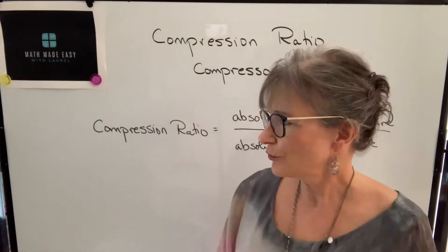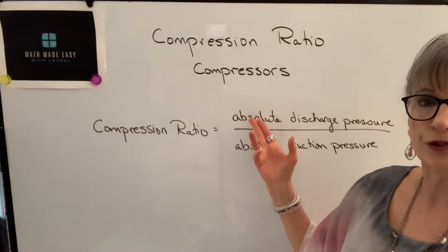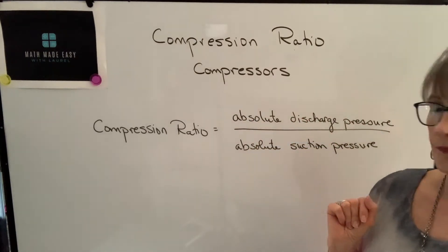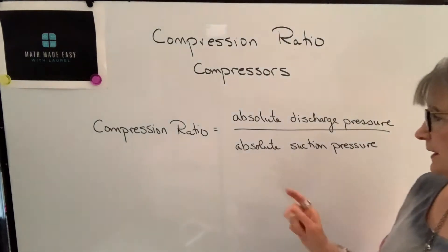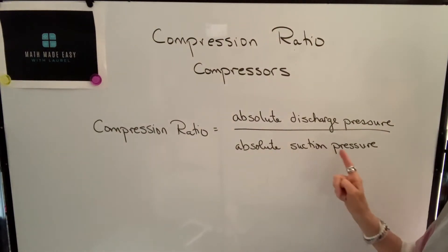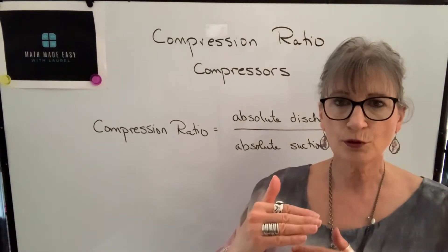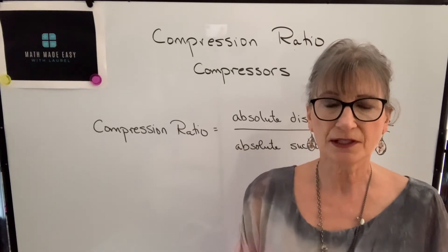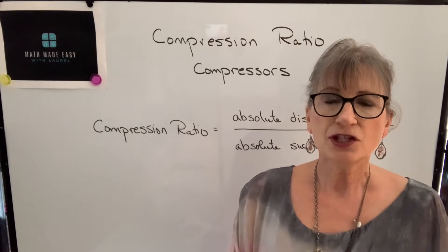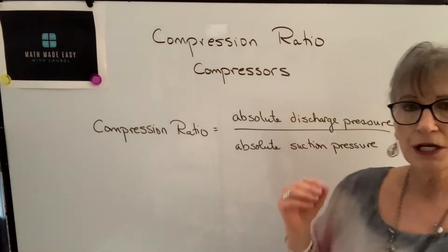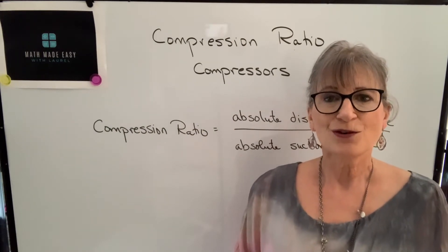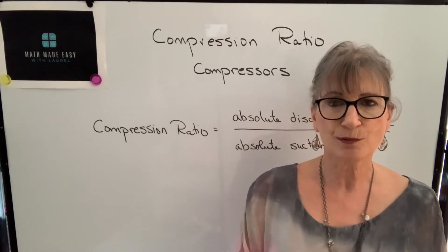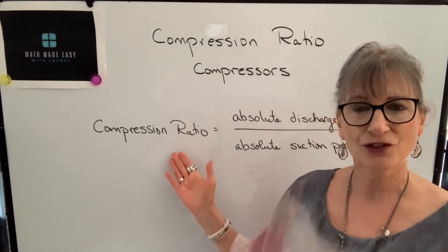The definition of a compression ratio is a ratio between two pressures in the compressor. The numerator is the absolute discharge pressure, and the denominator is the absolute suction pressure. Once they're in absolute units, you divide and get your ratio, expressed as something to one. The challenge is finding the absolute pressure, especially when working with vacuum pressures. I'll show how to convert vacuum and gauge pressures to absolute, then calculate the compression ratio.